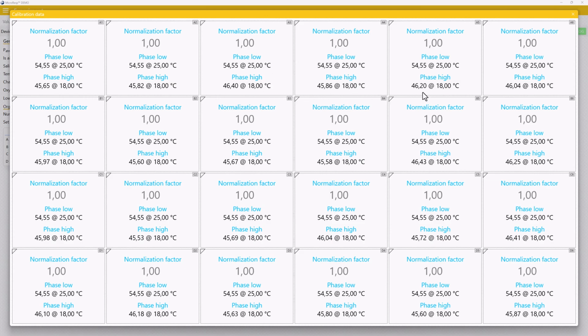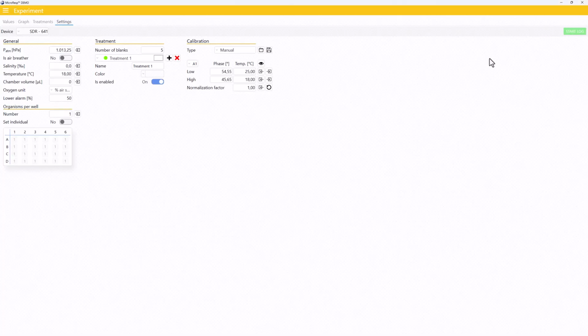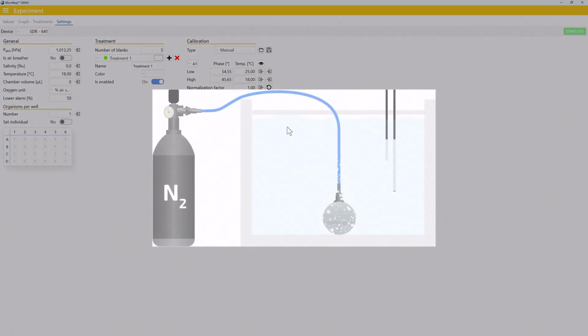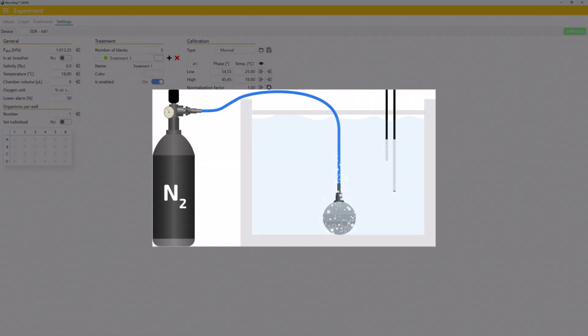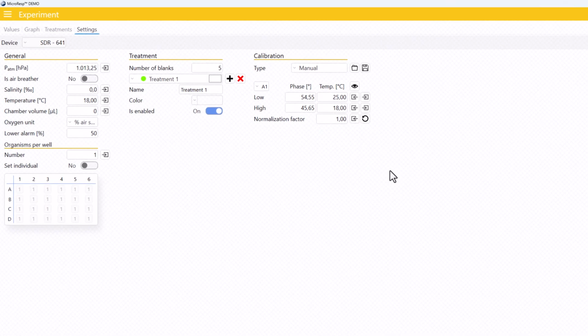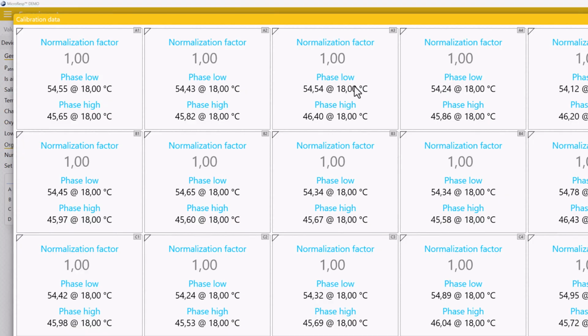Then fill the wells with the 0% air-saturated water sample. This oxygen-free water sample can be achieved by purging nitrogen gas into the sample water or by dissolving 10 grams of sodium sulfite in 500 milliliters of distilled water. Once the oxygen readings are stable, click this Read button again to read the 0 oxygen values. Again, the eye icon verifies the data now under phase low.